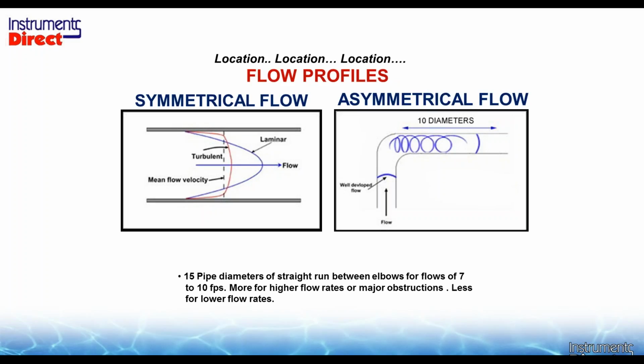Higher flow rates, if I had 20 feet per second, I need more straight run of pipe. If I had 5 feet per second, I could get by with less straight run of pipe. If I have a major obstruction like a pump or a butterfly valve or something that's really distorting the flow, I need more straight run of pipe. So hydraulics do play a role. You can't see all the time what's going on inside the pipe. What do I do if I don't have the required straight run of pipe, which of course has never happened? The generic rule is to go downstream 2/3 of the available footprint. So if I have 3 feet, go down 2 feet and put your sensor there. That's a starting point, and we'll look at some ways to try to get around that if we can.